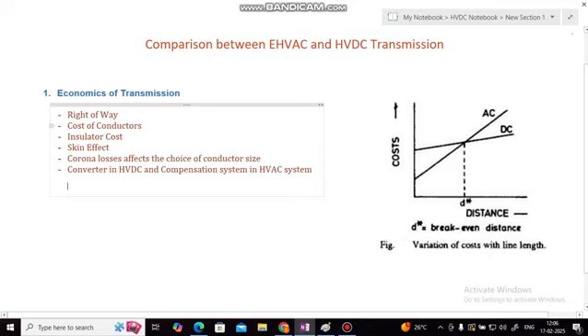And if we talk about the number of conductors, in HVDC system there are only 2 conductors, while in AC there are 3 conductors. So there is saving of cost in the installation of conductors in HVDC. While if we talk about the insulators, then for the same voltage rating, DC transmission requires less number of insulators because there are less number of conductors. So in terms of insulation, HVDC is beneficial. And if we discuss the skin effect, the skin effect is present in HVAC system. In DC it is not present. So HVDC is beneficial in terms of skin effect.